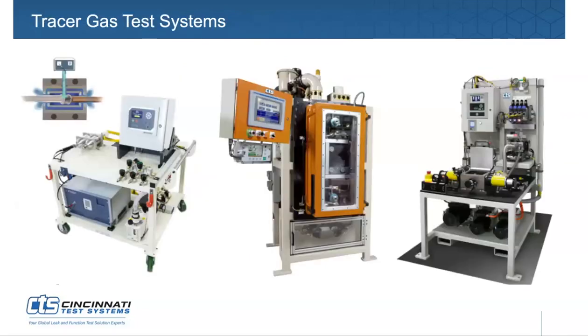And the test stands we just talked about were pressure decay and mass flow applications. We also supply instrumentation for tracer gas testing. Our TracerMate 2 instrument conducts manual sniffing on a cart, and it can also do automated purge clamshell testing. And then the center test stand is a semi-automated machine that's doing helium accumulation.